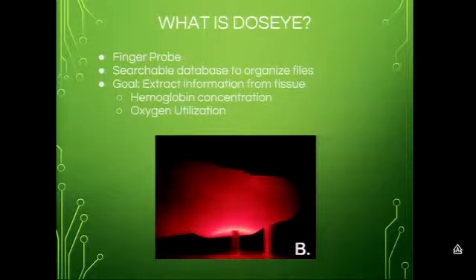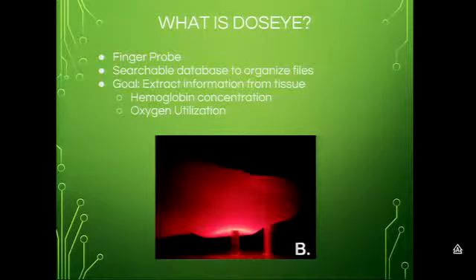What is DOSeye? It's an optical finger probe that will extract information from tissue. It has a source and a detector on it. The source shoots light through tissue, and the detector detects it on the other side. By comparing the detected light to the source light, we can extract information from the tissue, such as hemoglobin concentration and how much oxygen a person might be utilizing in their body, which can have a lot of health indications. We'll also be able to store the data we collect into a searchable database that can tag and store the data.